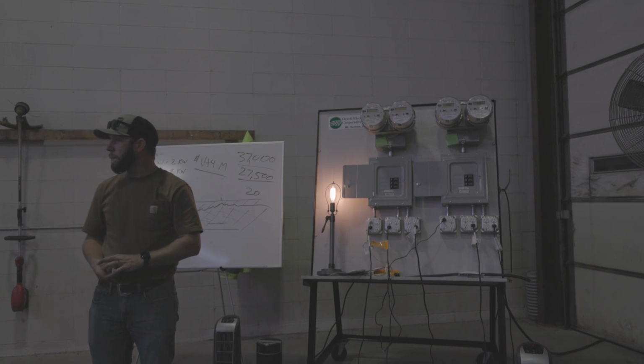Basically, they all occur at like 1,800 hours. Not all the peak ones did. I went back and looked at the base, because the peak ones are coincidental peak, which means it's all 25 substations at the same time. The base demand is non-coincidental, so each one of those 25 substations is looking at a different number.